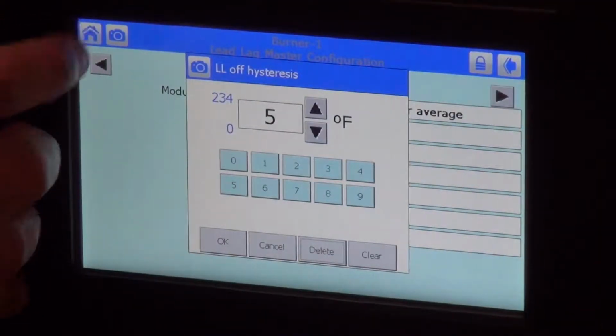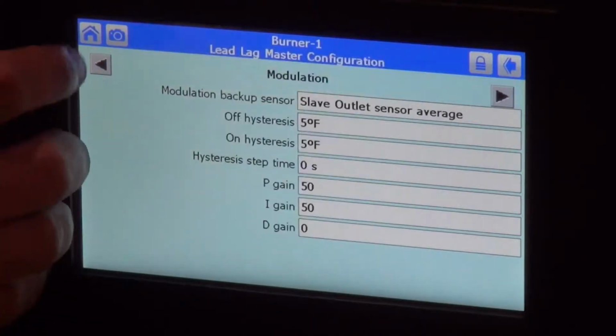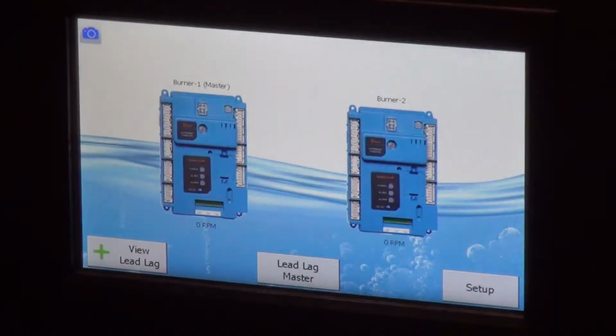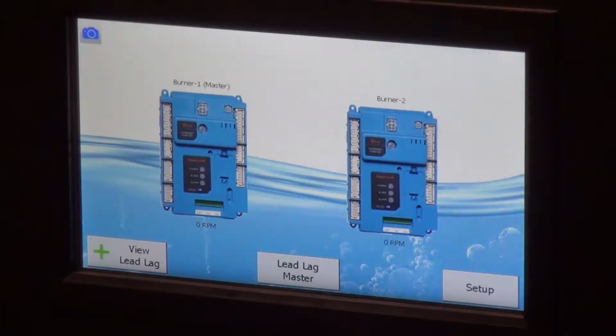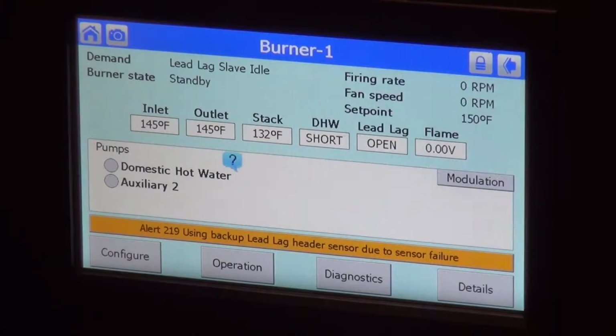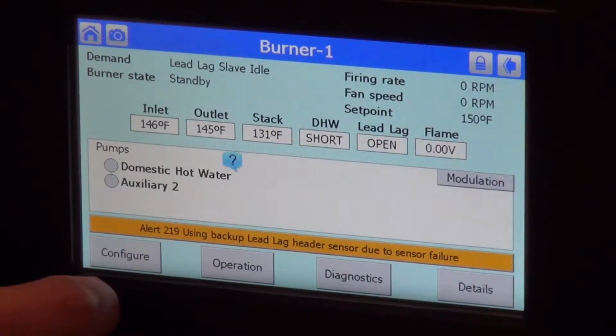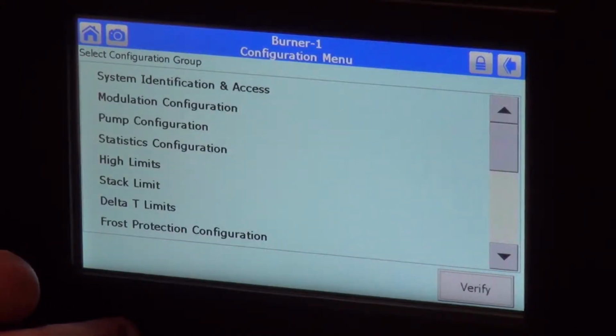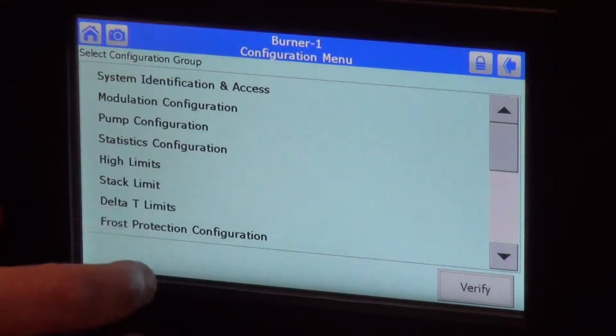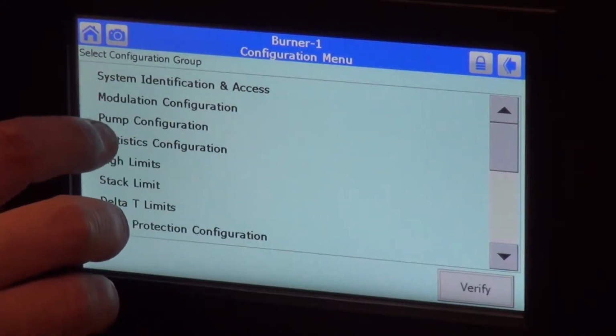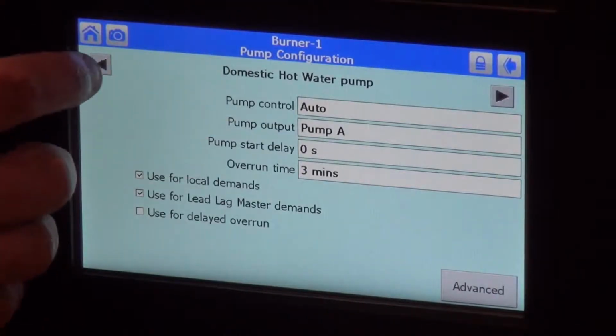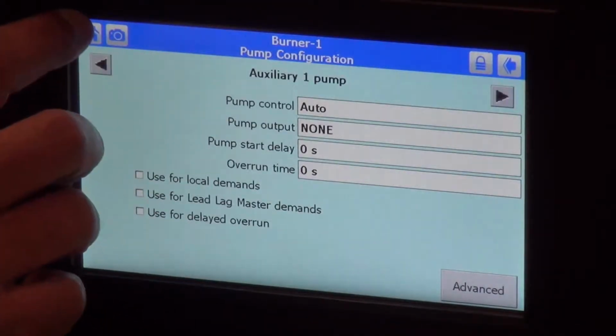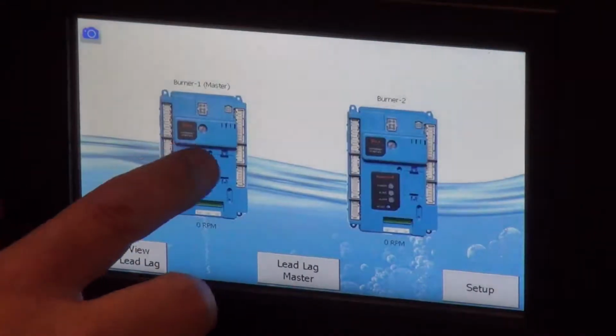Then we hit home. Come on. And then we're back. A couple other things to look at here. We can actually check if there's been fault histories on these guys, as well as the run cycles of each individual unit. In order to do that, we click on one of the burners on there. And when we click on one of the burners, we can hit on the configure. If we hit the configure button, then we've got some statistics we can look at. So we can look at pump configurations.